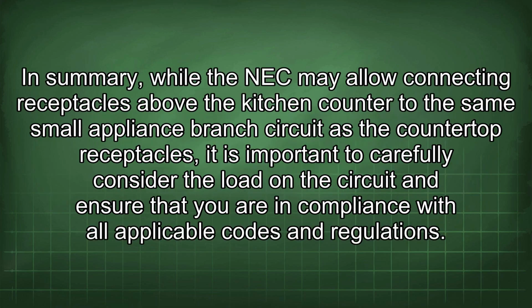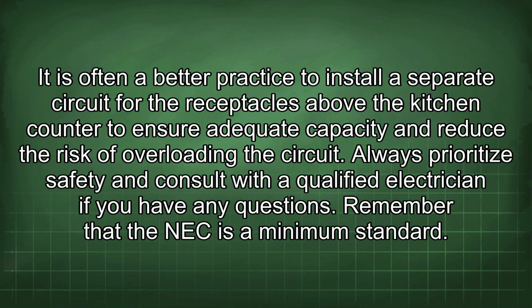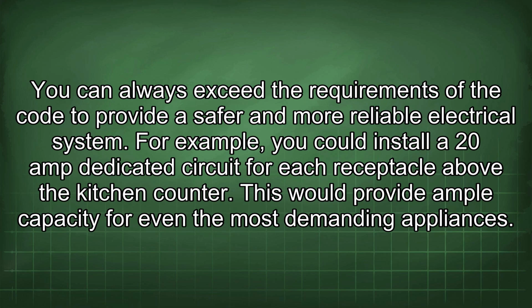In summary, while the NEC may allow connecting receptacles above the kitchen counter to the same small appliance branch circuit as the countertop receptacles, it is important to carefully consider the load in the circuit and ensure that you are in compliance with all applicable codes and regulations. It is often a better practice to install a separate circuit for the receptacles above the kitchen counter to ensure adequate capacity and reduce the risk of overloading the circuit. Always prioritize safety and consult with a qualified electrician if you have any questions. Remember that the NEC is a minimum standard. You can always exceed the requirements of the code to provide a safer and more reliable electrical system.